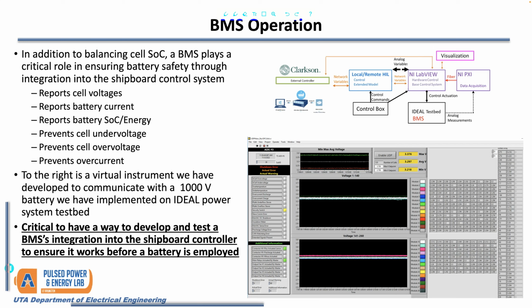In our case, all of this is important because these BMSs frequently integrate with external controllers, things like load shed and ramp rate. We rely heavily on the fact that these BMSs report correct cell voltages, monitor battery current, as well as SOC and energy, so we can estimate how much battery power is left. We also want to prevent scenarios such as cell under voltage and cell over voltage, which would permanently damage the cells, and prevent overcurrent, which might damage the cells or cause thermal runaway. So it's critical that we have a way to test this BMS before we implement it on the 1,000-volt battery, so we can guarantee it will operate in the condition we expect.